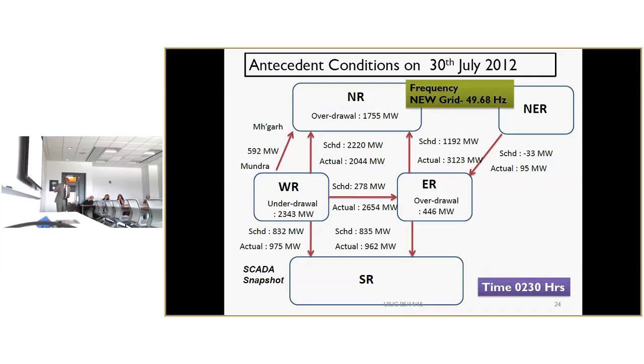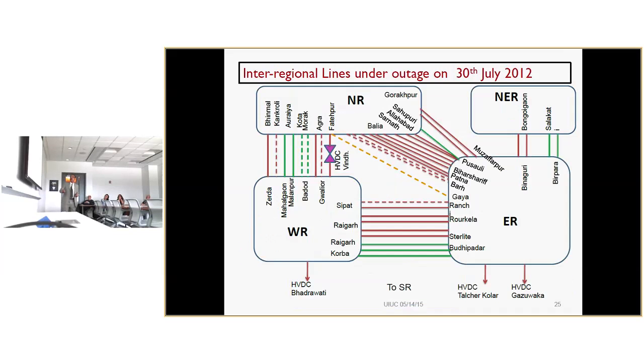And that was a very unfortunate day. A lot of lines in the western region, on the boundary of the northern region, went either on forced outage or were on scheduled outage, including the inter-regional interconnection, because some of the lines we were upgrading to 765 kV from 400 kV, and that was out. And a few lines which were supporting the flow, even 220 kV lines, went one by one. Finally, if you see the line situation, these are the lines which were out, the dotted lines were out.